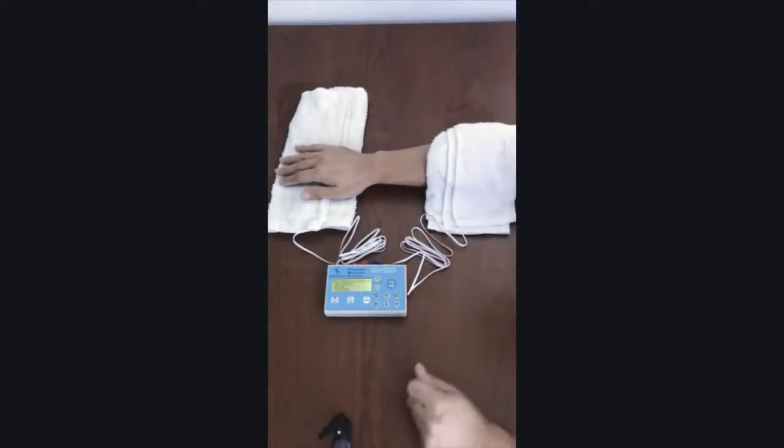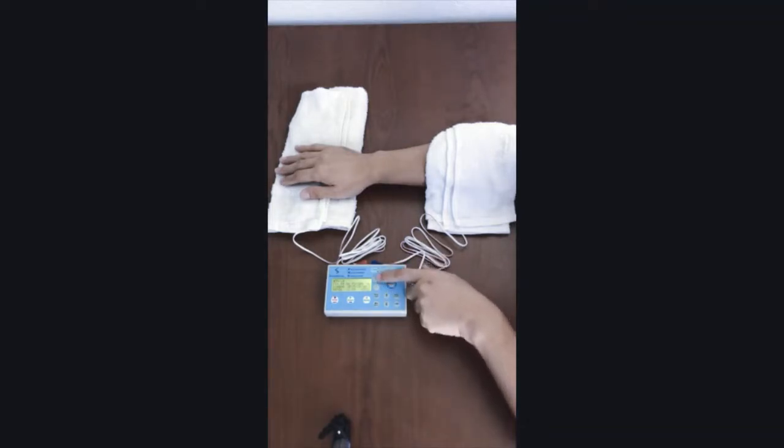To run a therapy protocol, just press the start key. The protocol will start to run and you can see the protocol running information on the screen. To change the output current intensity, press the plus key to increase the current intensity value or press the minus key to decrease the current intensity value.